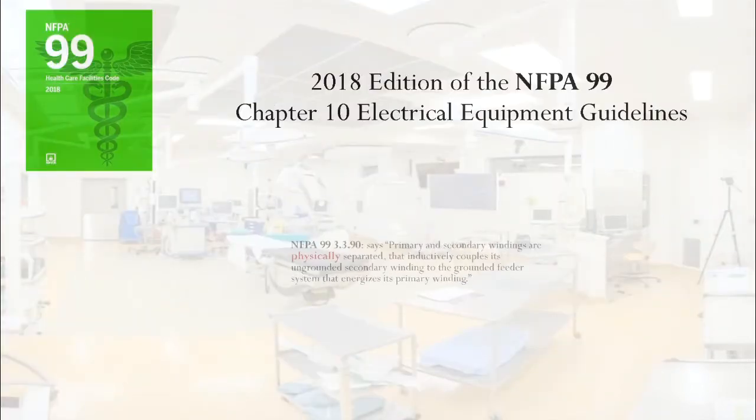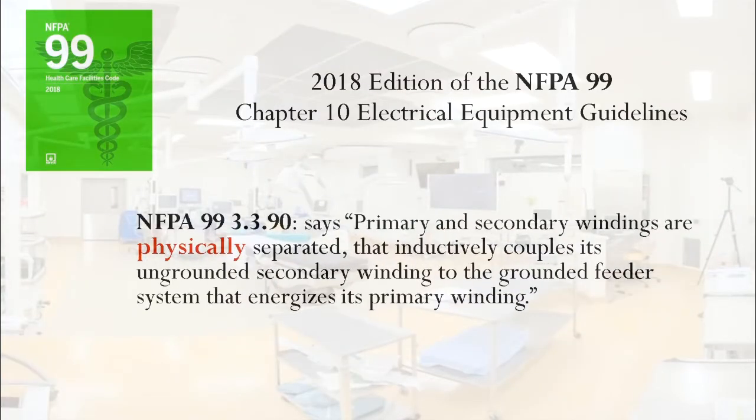NFPA 99 3.3.90 says primary and secondary windings are physically separated, that inductively couples its ungrounded secondary winding to the grounded feeder system that energizes its primary windings. Simply put, located in the isolation transformer are the primary and secondary windings. The primary windings are not referenced to secondary windings — they don't touch each other.